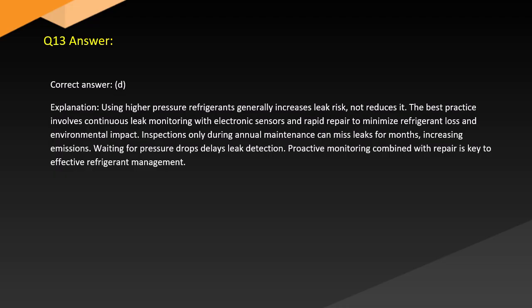Answer. Correct answer, D. Explanation. Using higher pressure refrigerants generally increases leak risk, not reduces it. The best practice involves continuous leak monitoring with electronic sensors and rapid repair to minimize refrigerant loss and environmental impact. Inspections only during annual maintenance can miss leaks for months, increasing emissions. Waiting for pressure drops delays leak detection. Proactive monitoring combined with repairs is effective refrigerant management.